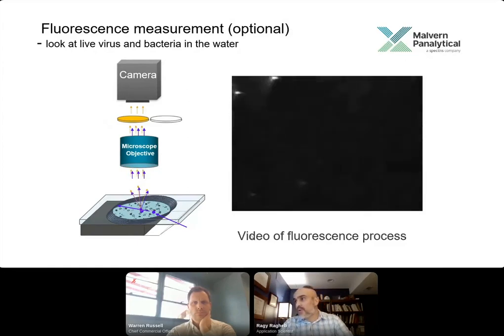You'll see here that the filter is being inserted, particles disappear for a moment, and you can now see just fluorescently labeled particles and do all the same analysis, and then do some profile comparisons where you can look at the size differences between those that are fluorescently labeled compared to those that are not, or what the concentration of those fluorescently labeled is compared to the total population.